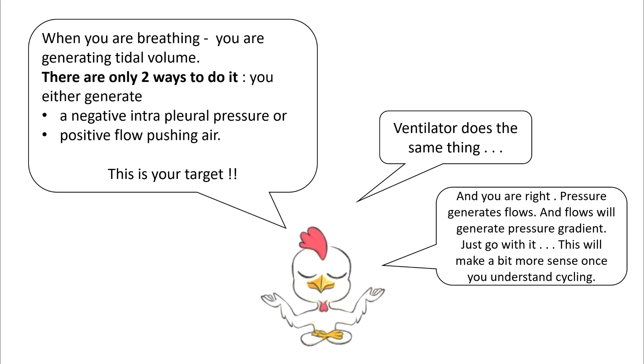So target is how your breath is delivered during the inspiration, and it is the variable that you use to give the breath, and this variable is not exceeded. For example, if you set a flow at 40 liters per minute, that flow is going to generate a tidal volume. And if you set pressure, for example 20 centimeter of water pressure, that pressure is going to generate a tidal volume as well. The ventilator is not going to exceed these limits.